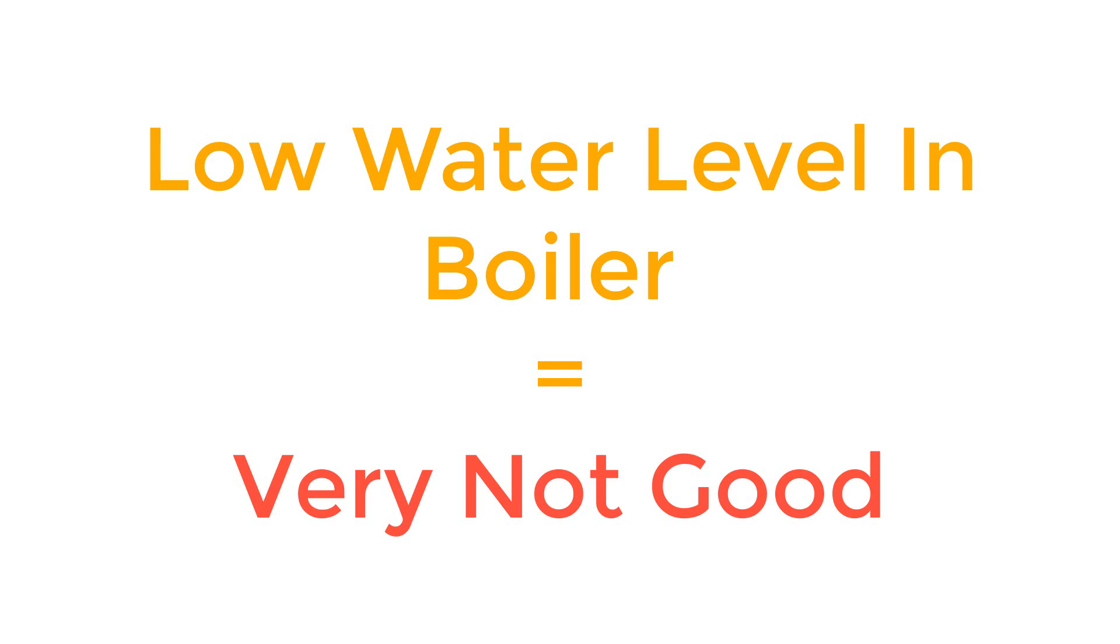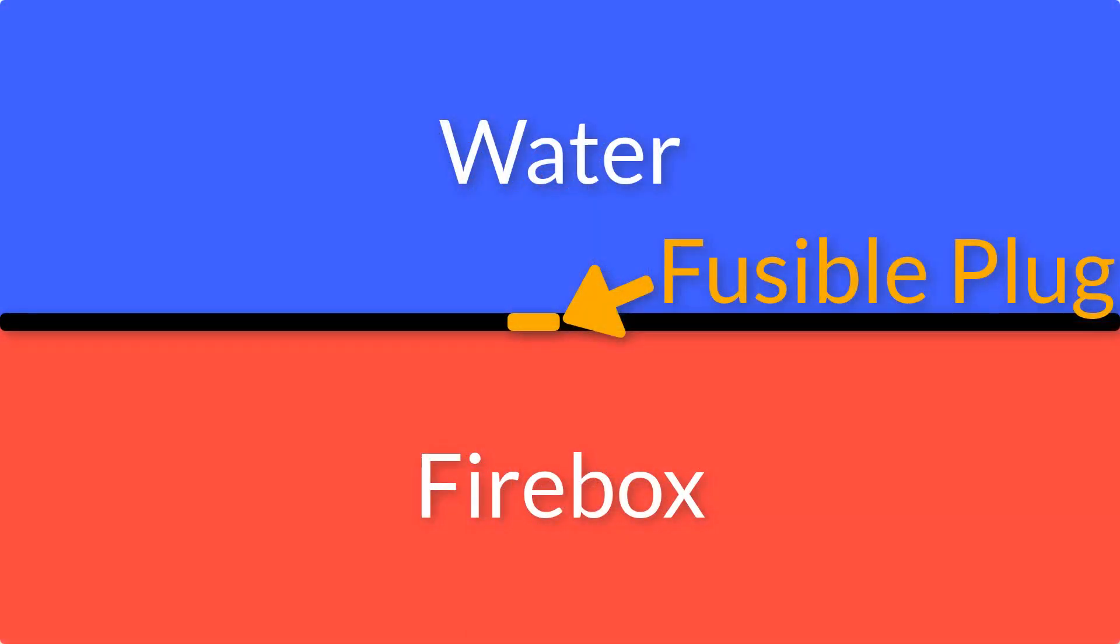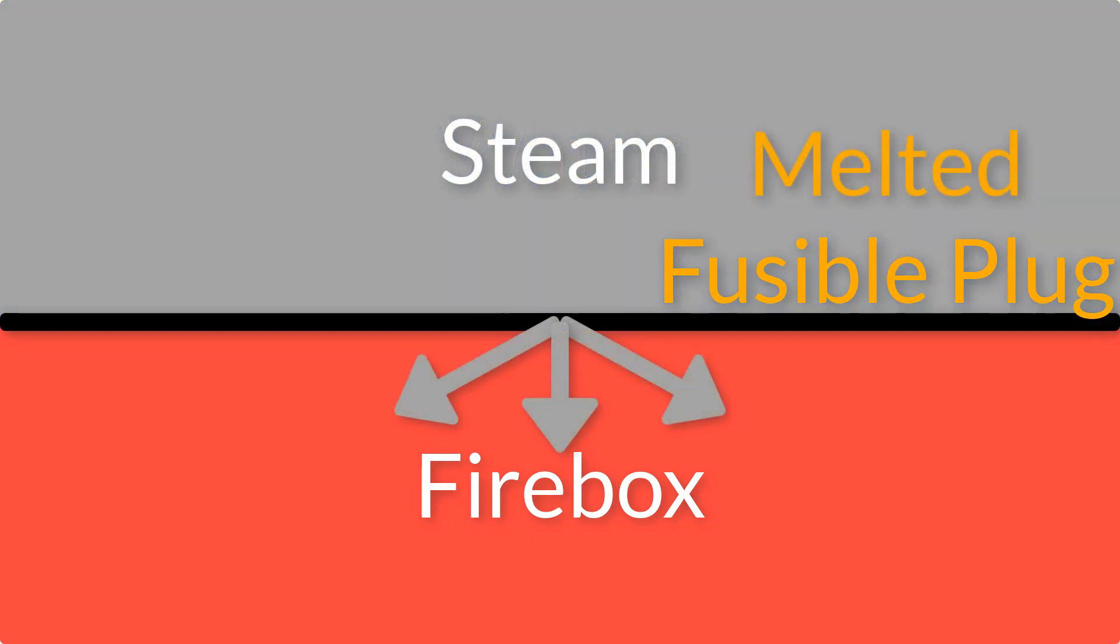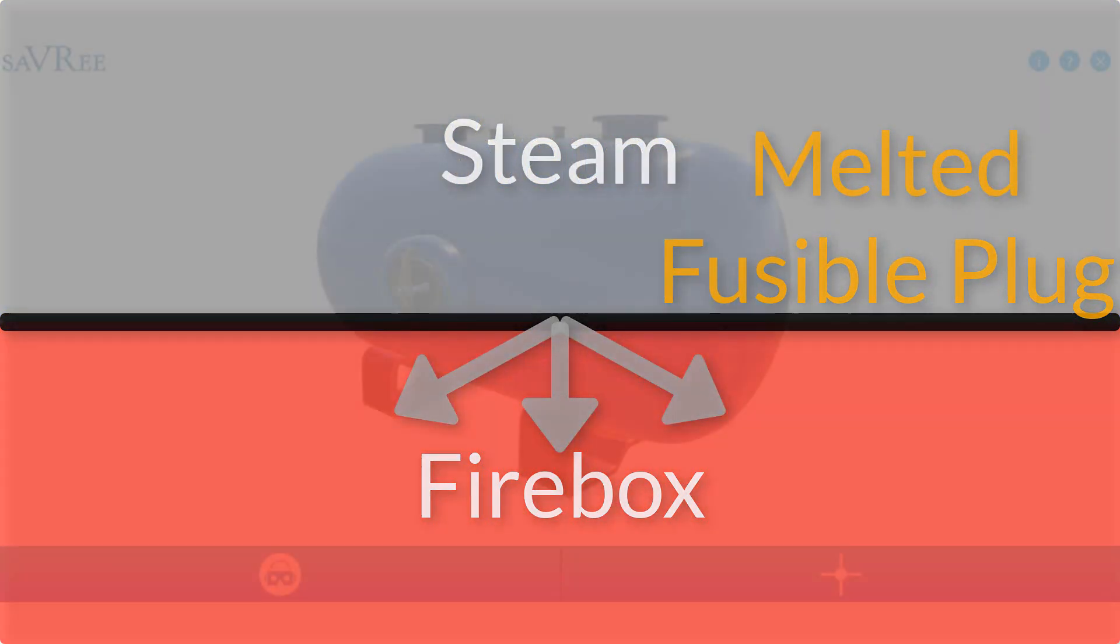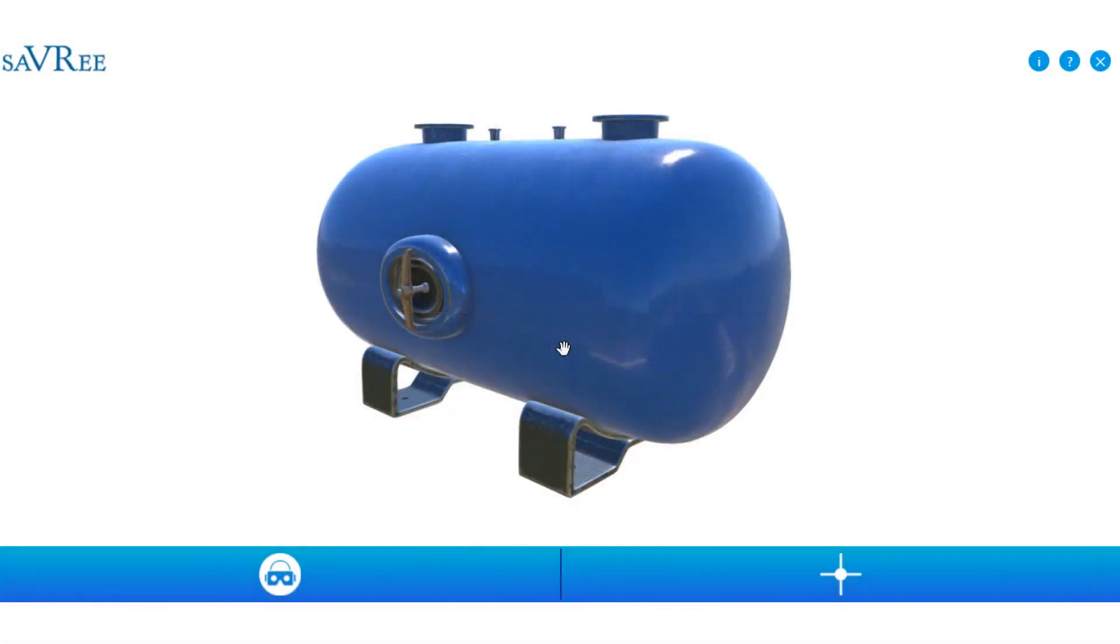The steam and the elevated temperature would melt the fusible alloy and the steam would then enter the furnace space or the firebox and it would extinguish the fire as well as vent the steam, at least to the firebox. But this was an absolute last precaution, and nowadays fusible plugs in boilers are more of a rarity than standard.